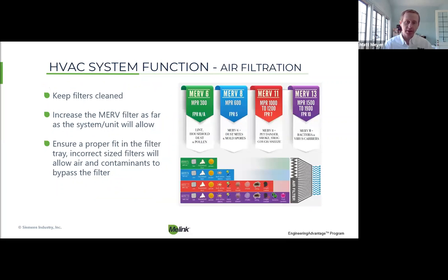You can jump to the next slide. So this is touching on filters. And I know Tim briefly touched on filtration and with the BMS systems and how it kind of interrelates. So keeping your filters clean, Tim was talking about, the BMS systems can let you know when your air filter starts to become too clogged or too dirty. That's great. And that's a really big benefit of the BMS systems that are out there, because they can start to help maintenance providers understand what's going on with the building before it actually becomes a major issue.